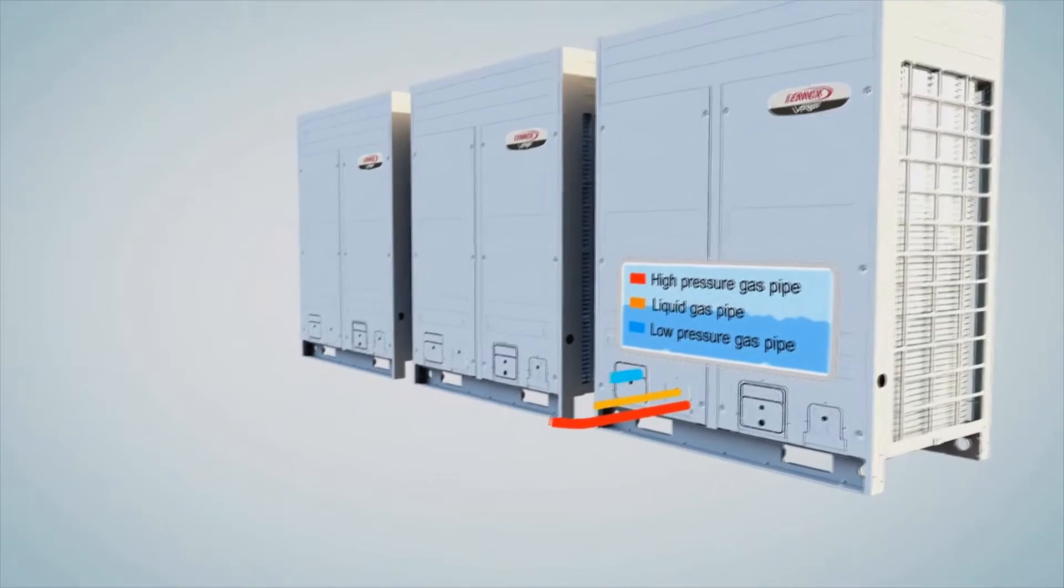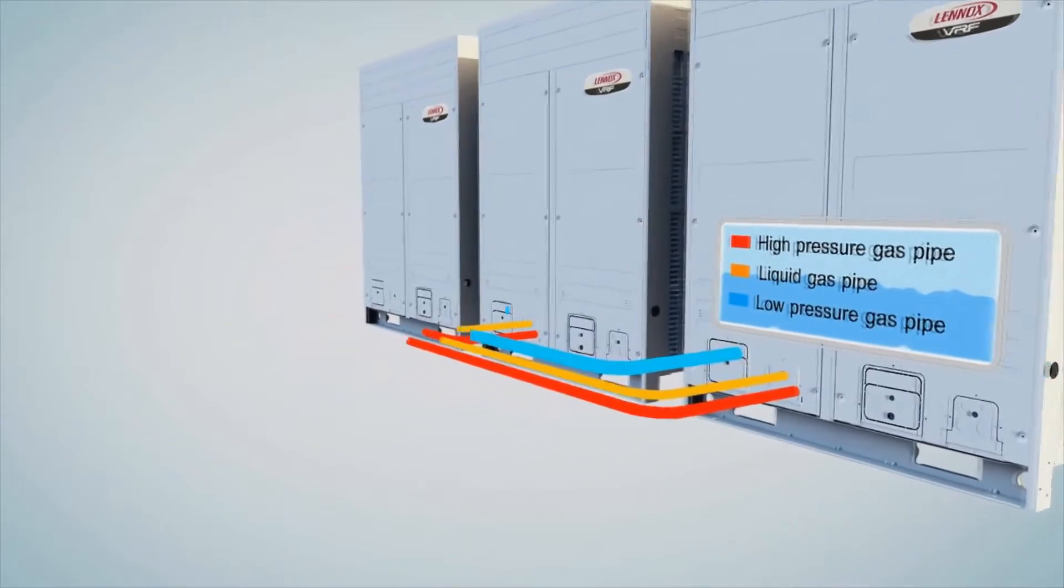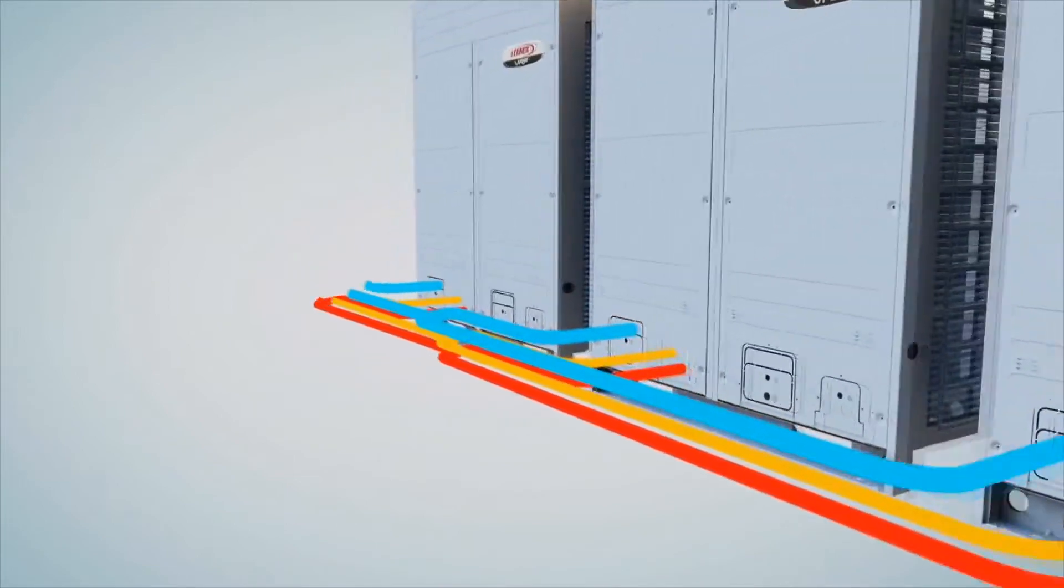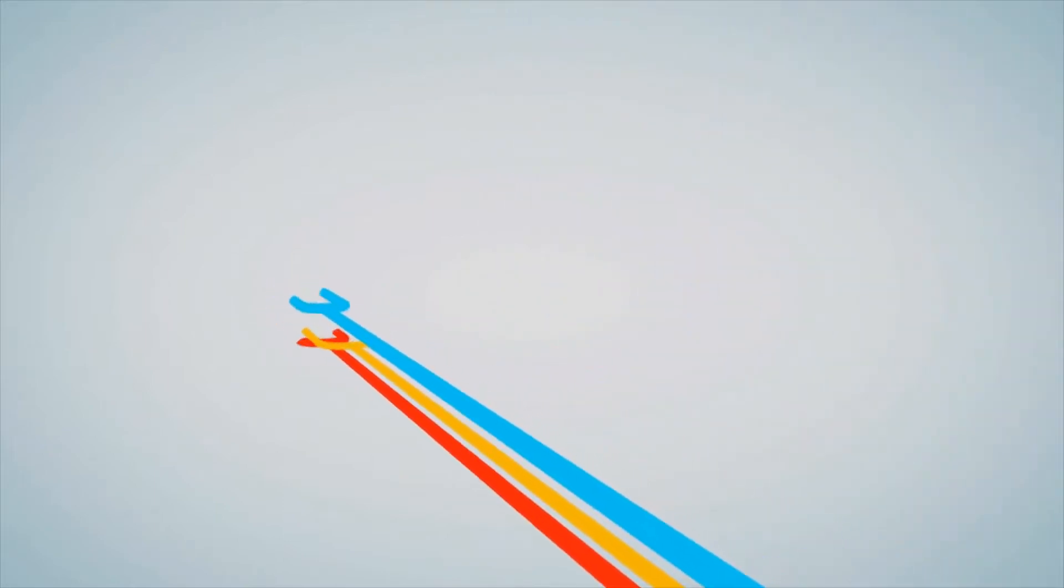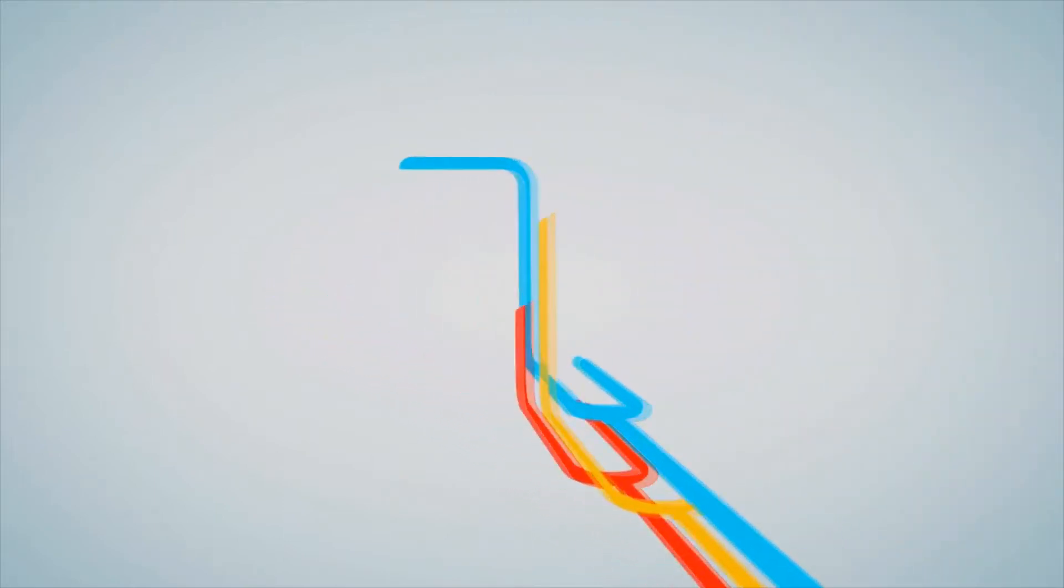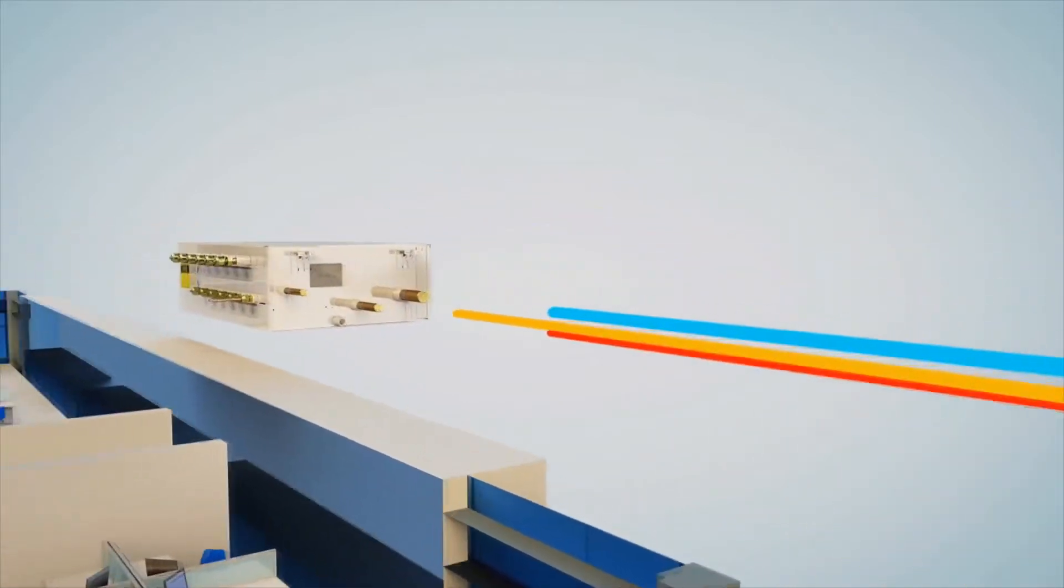Let's take a closer look at the Lennox VRF system. Three refrigerant pipes connect the outdoor units to the MS boxes: Liquid, suction or low pressure gas and high pressure gas. The MS box controls the direction of refrigerant flow through the indoor units.